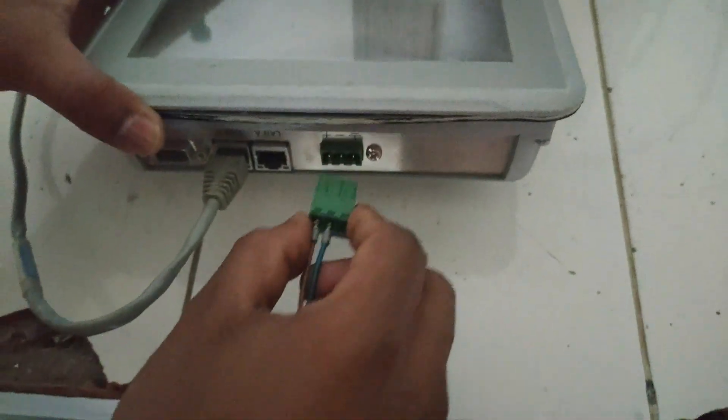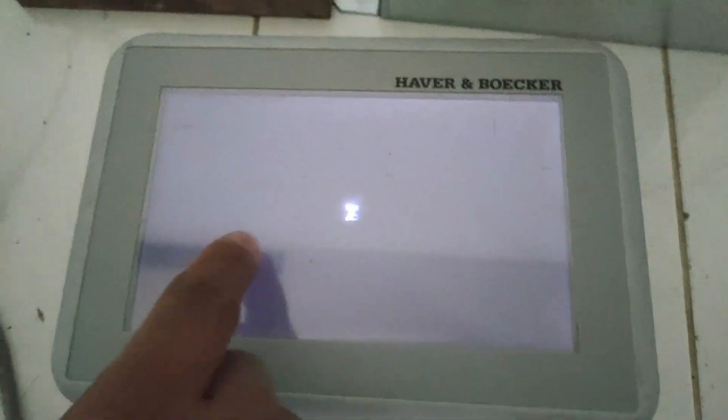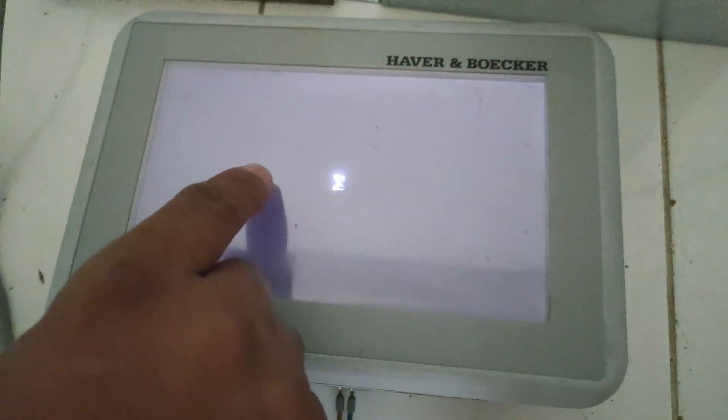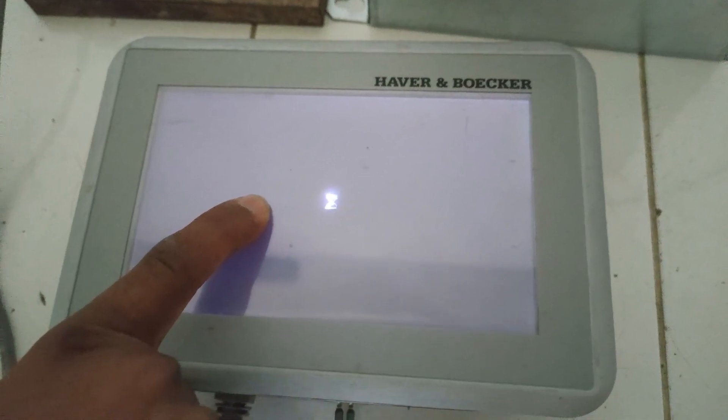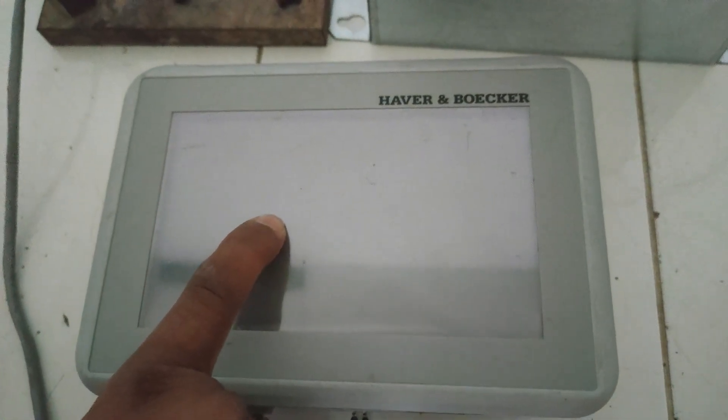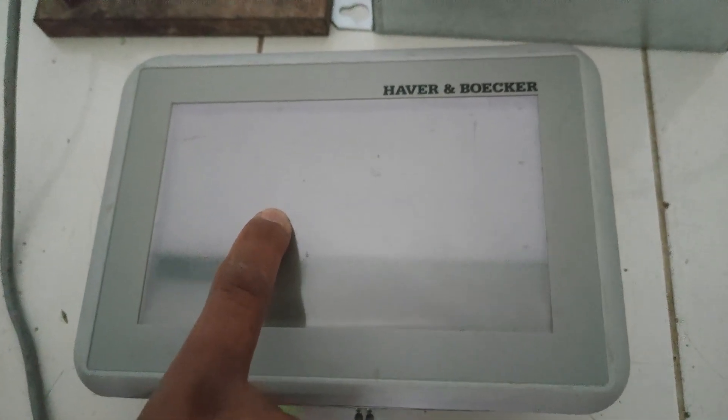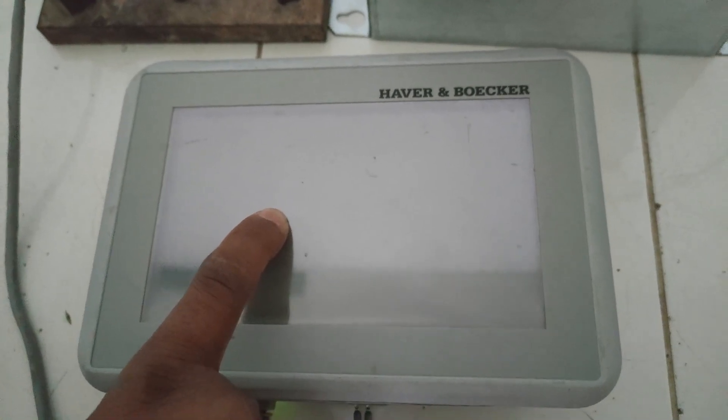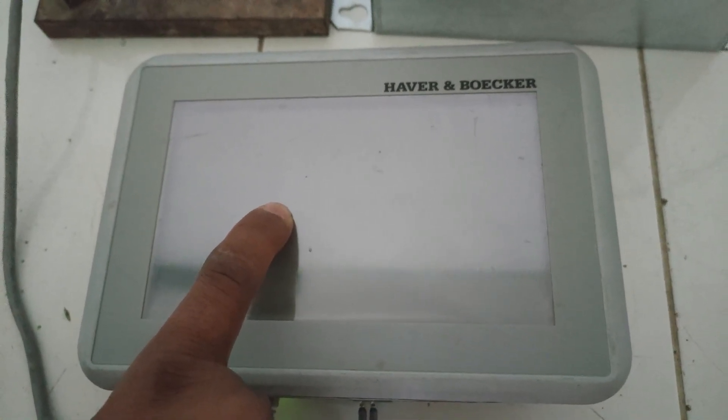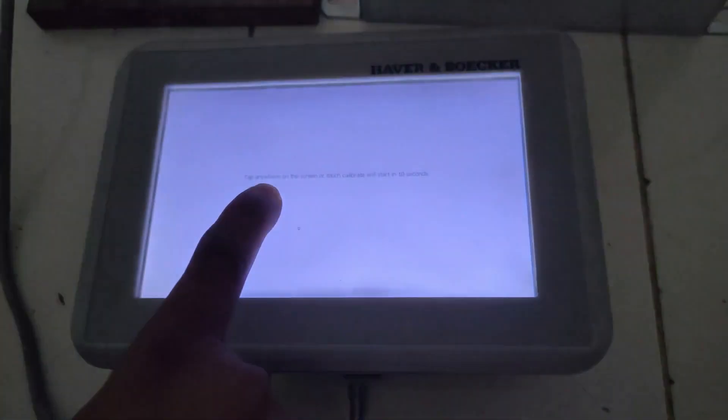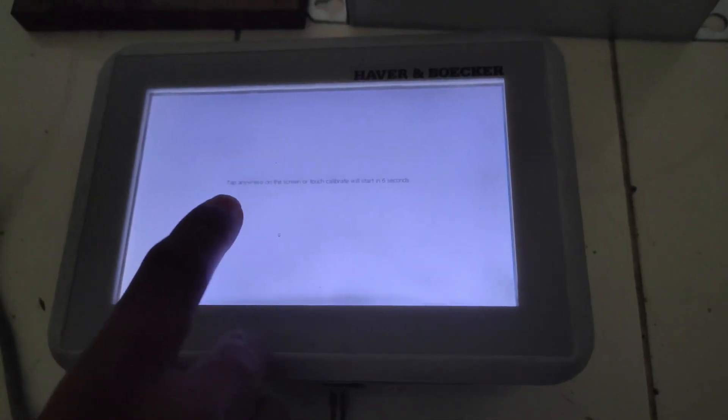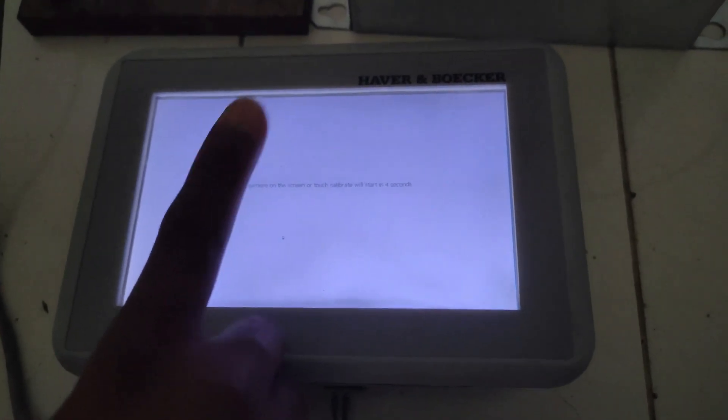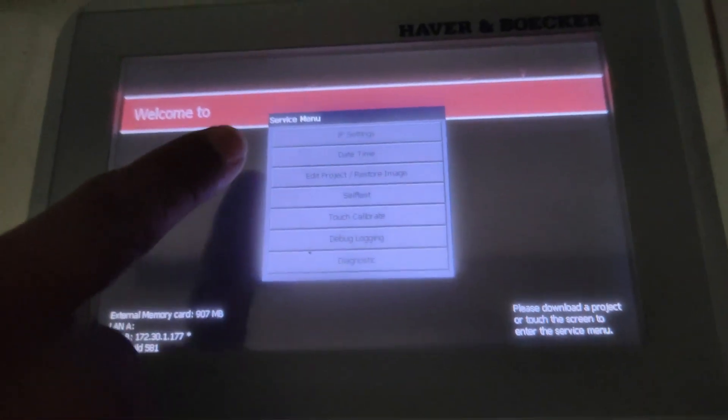I am going to turn off the power of the HMI and turn it back on again, and touch the HMI screen to go to the service menu. When the white screen comes, you have to touch again, release, and touch again within 10 seconds. Then you will enter the service menu.